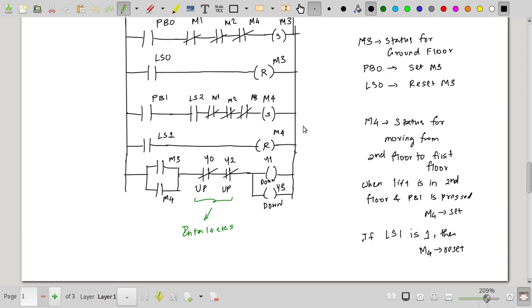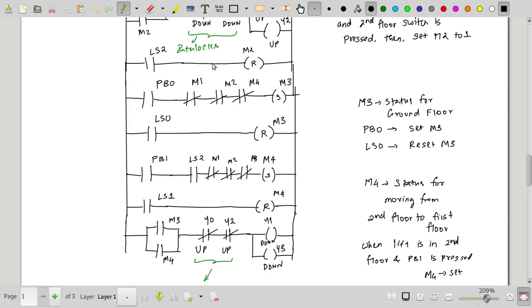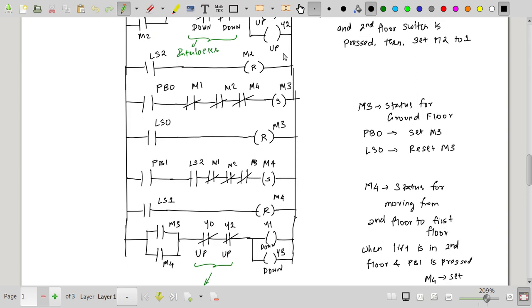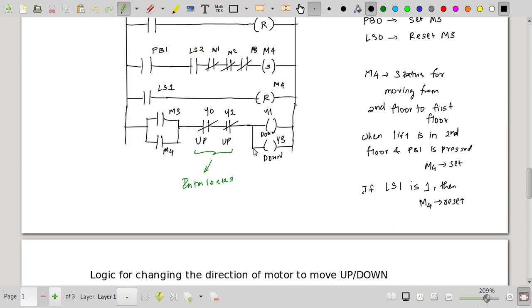Both M3 and M4 represent downward movement. Using these status flags, we enable the downward movement of the motor. The last rung in the ladder: when M3 is on or M4 is on, and as a safety interlock Y0 is not on and Y2 is not on, then Y1 and Y3 are turned on. Here also we have an interlock — if it is not moving up, then we move down. This program ensures that Y0, Y1, Y2, and Y3 are never all turned on at the same time.